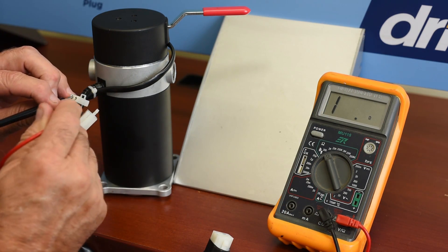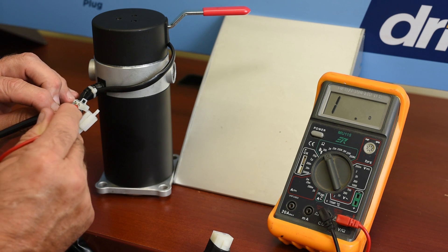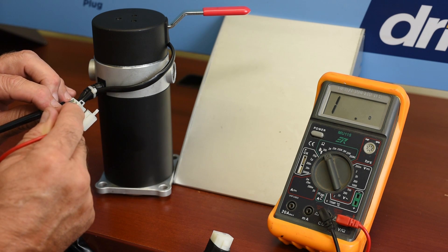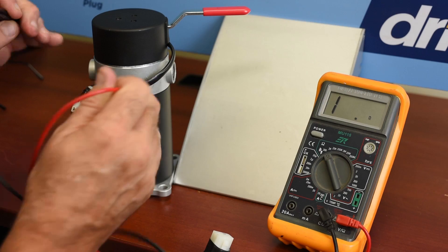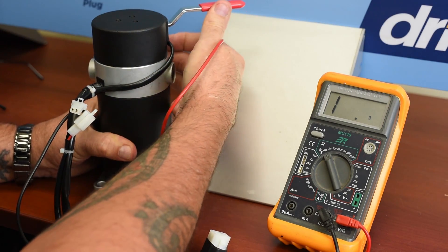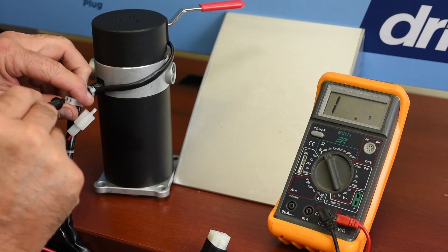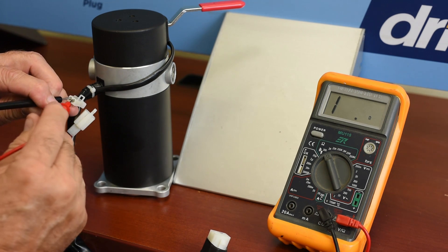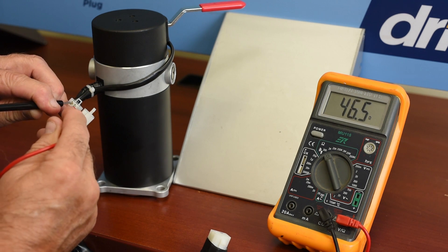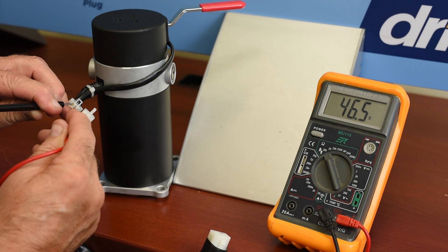We'll take the leads, plug them back in again, and we have an open circuit. We put it back in to make sure everything is working again. We plug the leads back in and we got 46.5 ohms again, and we have a very good motor brake.